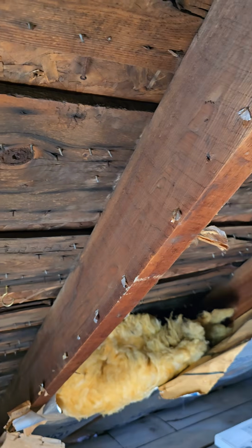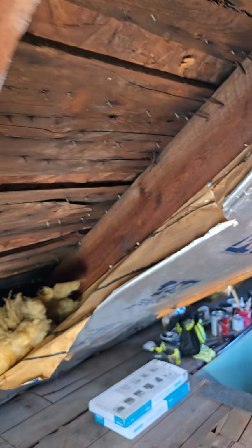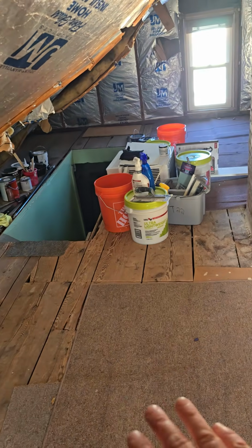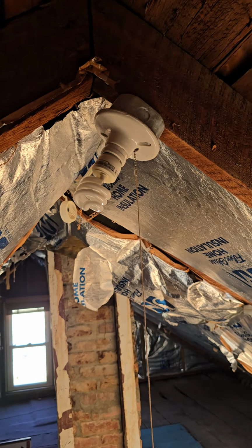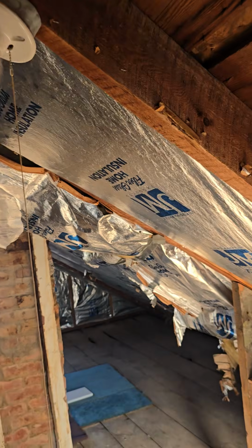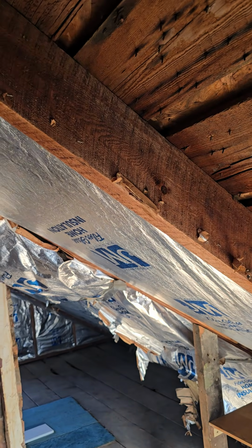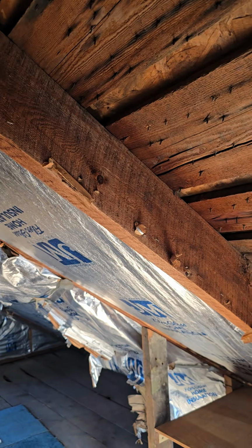So you really need to pick a road when you do insulation. Either insulate directly above the conditioned area, or if you're going to insulate the ceiling, you have to have ridge vent and soffit vent and proper airflow to avoid overheating the roof and avoid the mold and the moisture that gets trapped there.